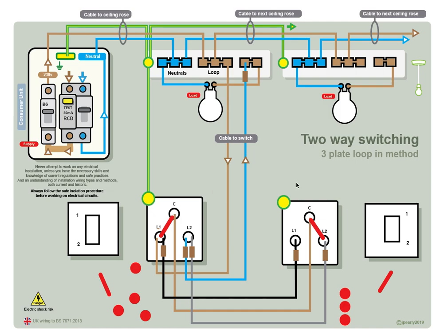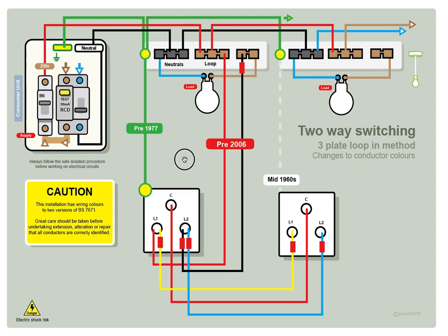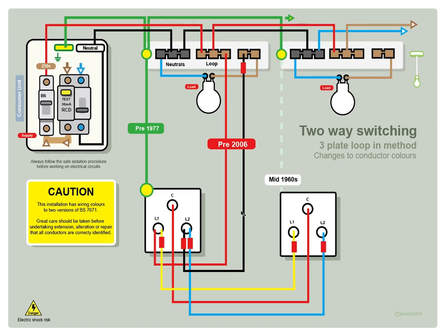This is with the modern colors, but go back a few years pre-2006, they used to have different colors for their conductors. The line color was red, neutral was black, and the strap colors were red, yellow, and blue. So you might see this. You might open a light switch and you might see this color arrangement. Same principle, just different colors.